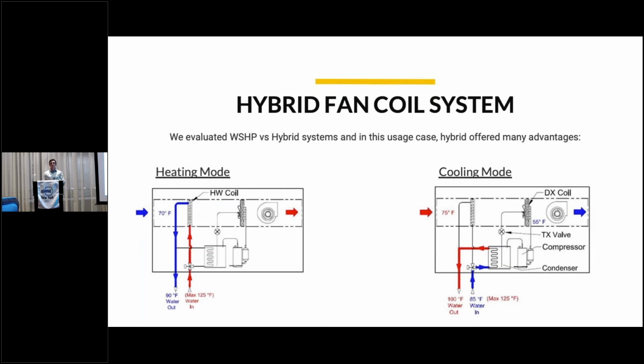And then in cooling mode, we have a standalone DX system that's in that fan coil with its own coil, but it's rejecting its heat instead of to an outdoor condenser. It's actually rejecting its heat back into the hydronic network. So we're keeping as much heat as possible in the system so that we don't have to fire up our heat pump and we don't have to fire up our condensing boiler unless the temperature rises or falls by a significant amount. And because each unit has one of these, it can operate in heating or cooling mode whenever it wants.